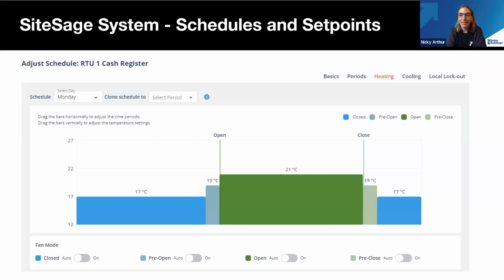The schedules are set relative to opening and closing hours, so if we tweak the opening and closing times, the schedule adjusts accordingly. Along the top here you can see the cooling schedule, which is similar, with a set point of 23 degrees C. The staff have some local control in the stores—they can tweak the thermostats up or down by about 2 degrees in either direction, and at the end of that period it reverts back to the schedule.